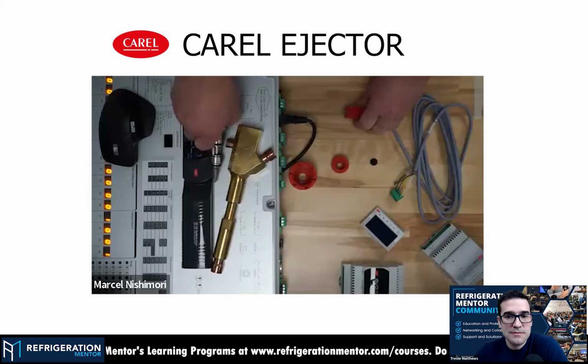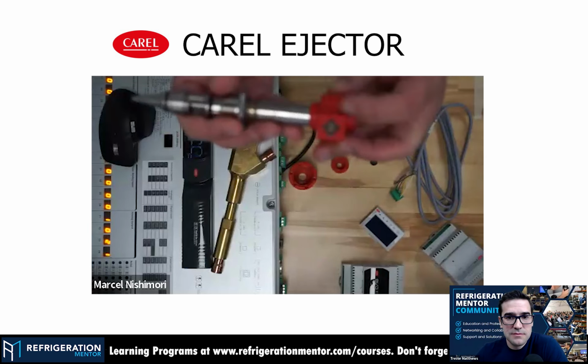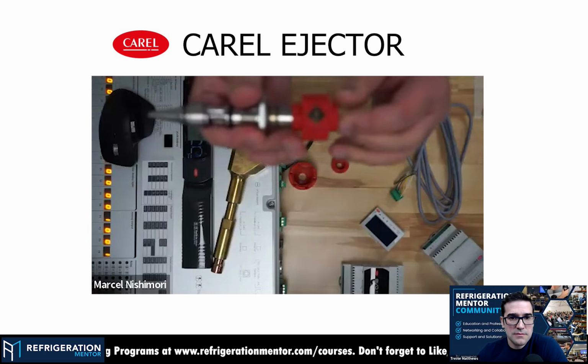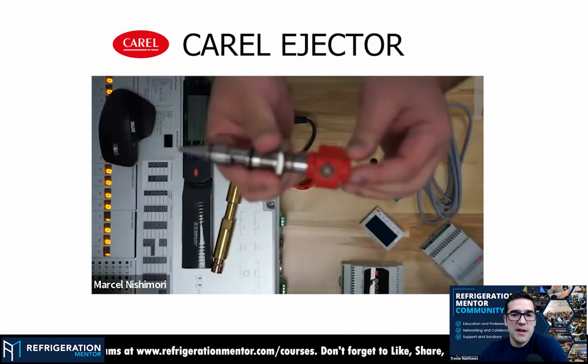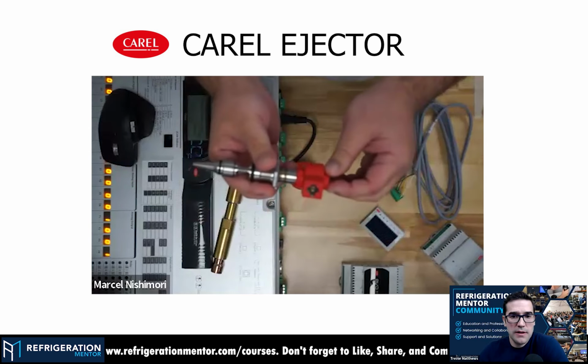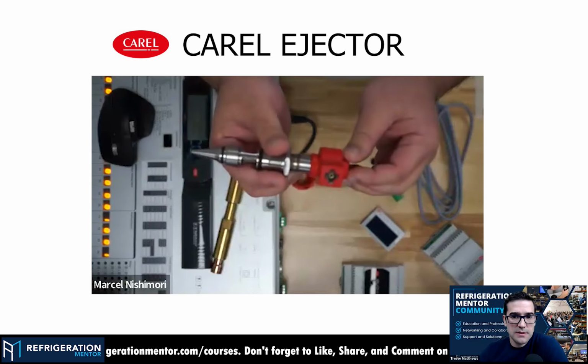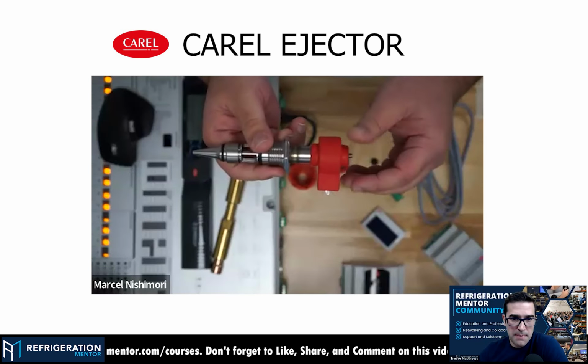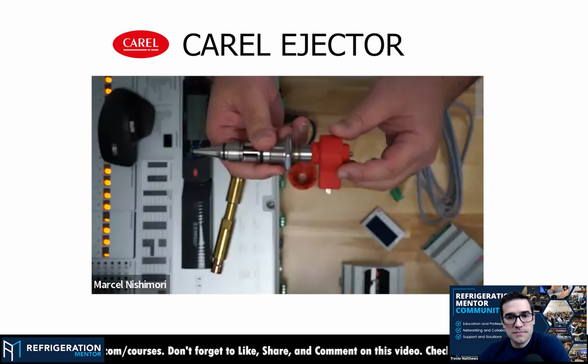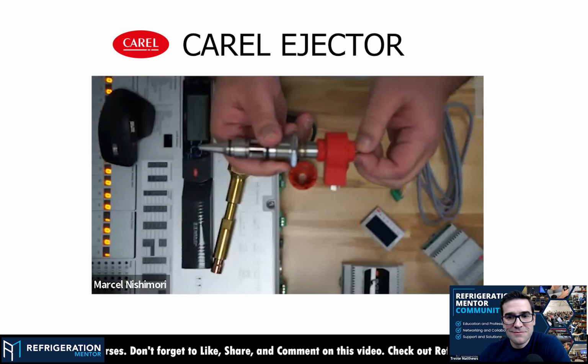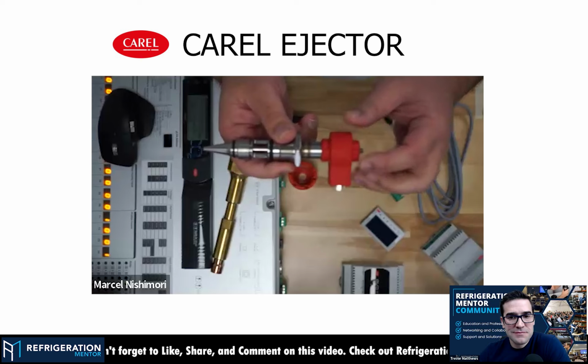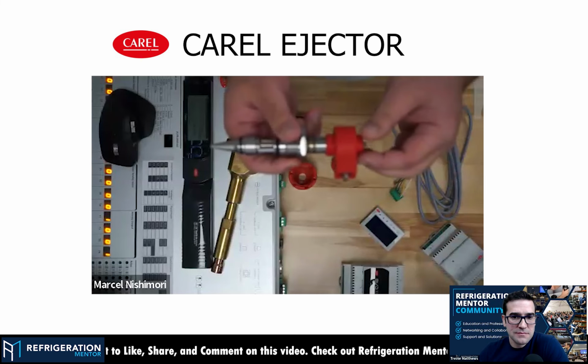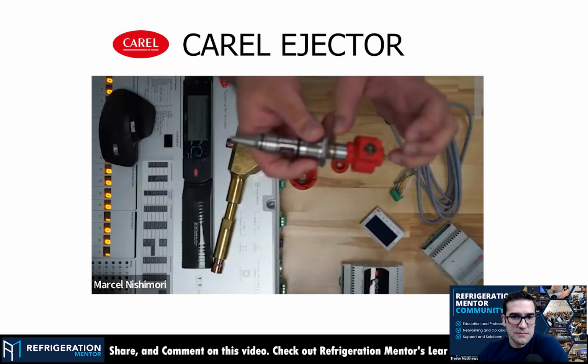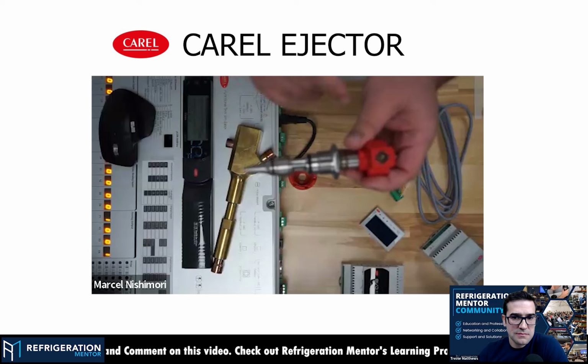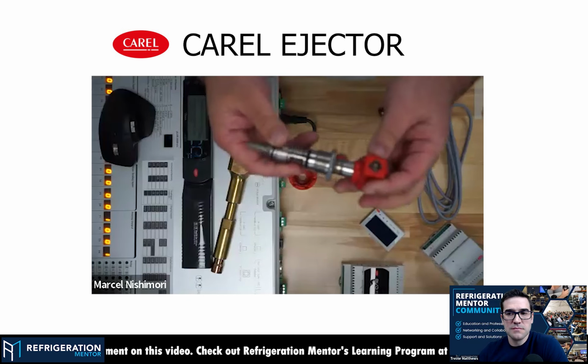Yeah. So, how do we control this needle? We have the stator here. It's the same as our electronic expansion valves. Lower, Marcel, it's just blurry. No, lower. Yeah, there we go. Right there. Okay. So our stator is the same as our stepper motor valves for the electronic expansion module. And this motor can be connected to a bipolar CAREL driver, and we can precisely adjust the flow inside the ejector.